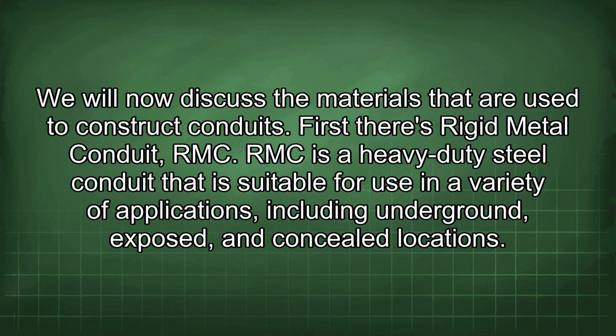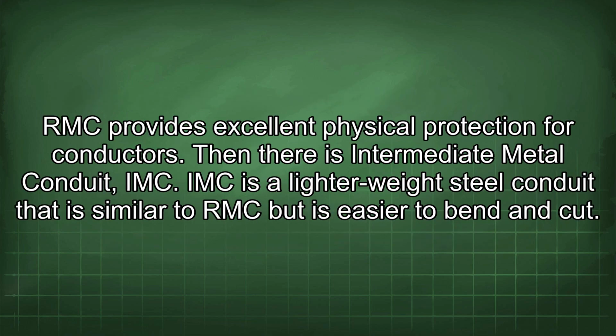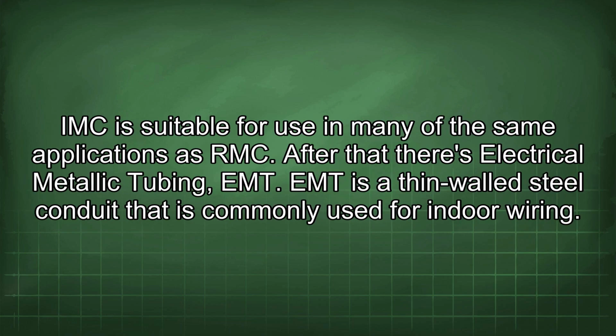First, there's rigid metal conduit, RMC. RMC is a heavy-duty steel conduit that is suitable for use in a variety of applications, including underground, exposed, and concealed locations. RMC provides excellent physical protection for conductors. Then there's intermediate metal conduit, IMC. IMC is a lighter weight steel conduit that is similar to RMC but is easier to bend and cut. IMC is suitable for use in many of the same applications as RMC.